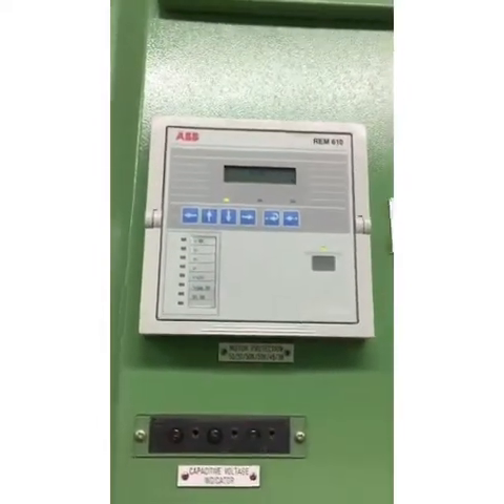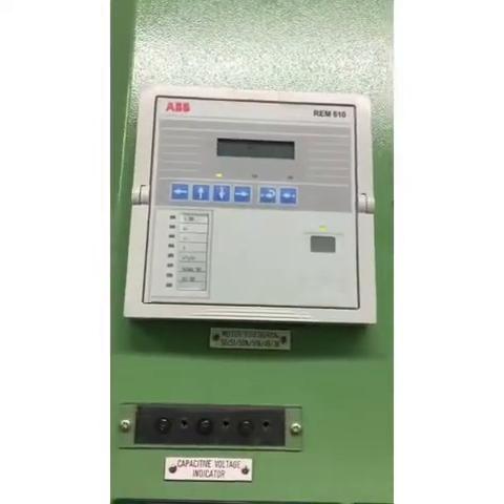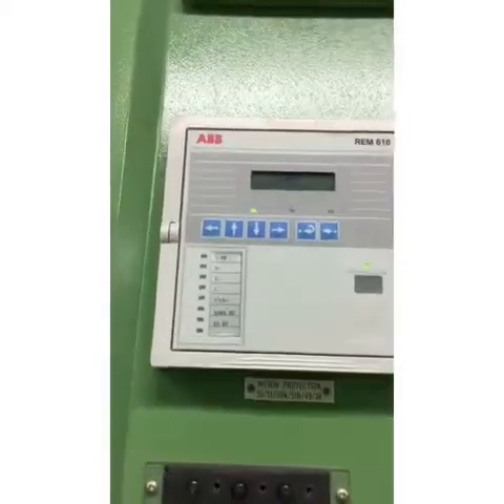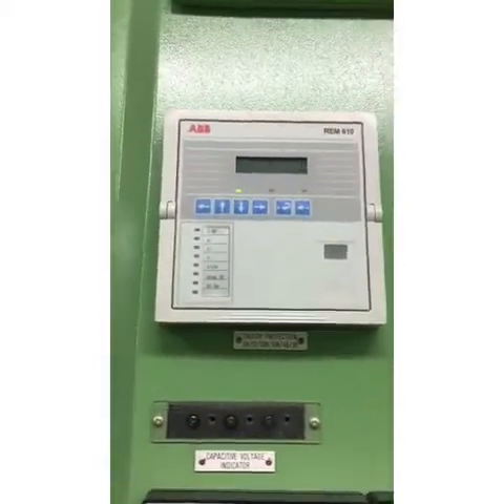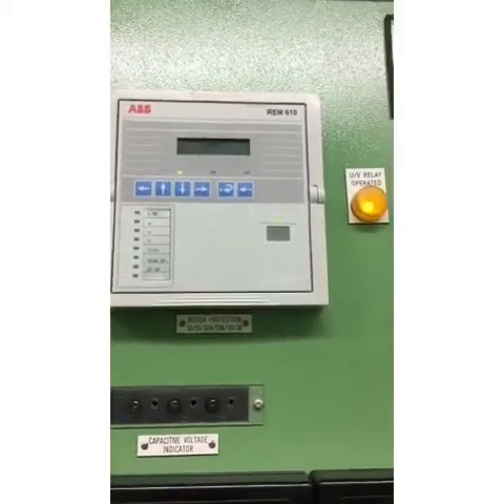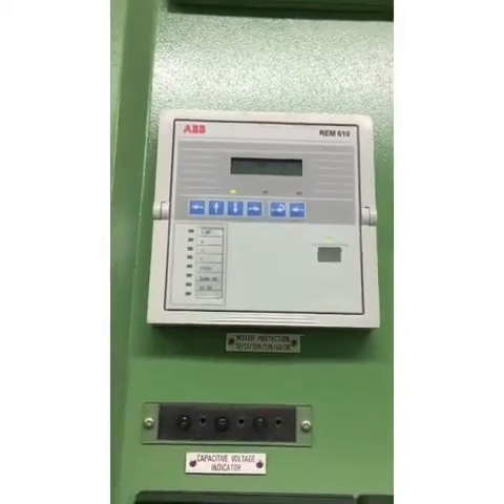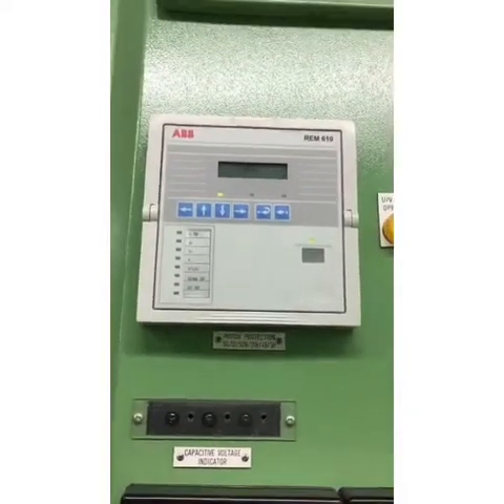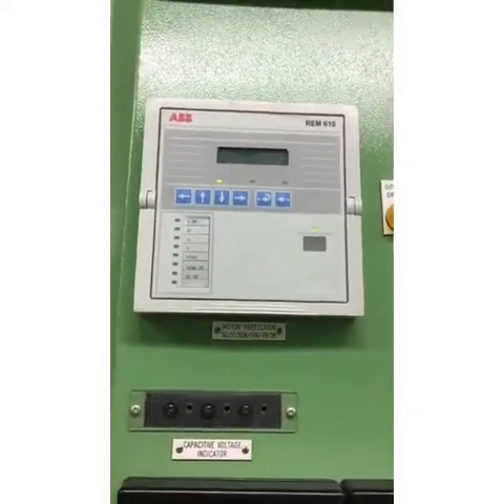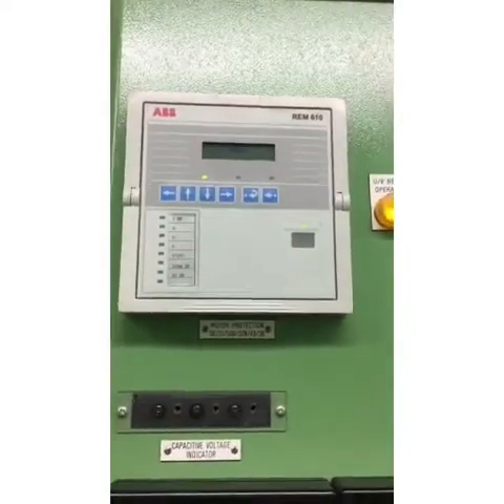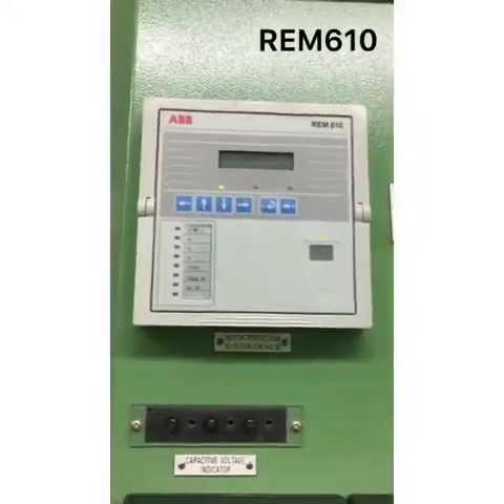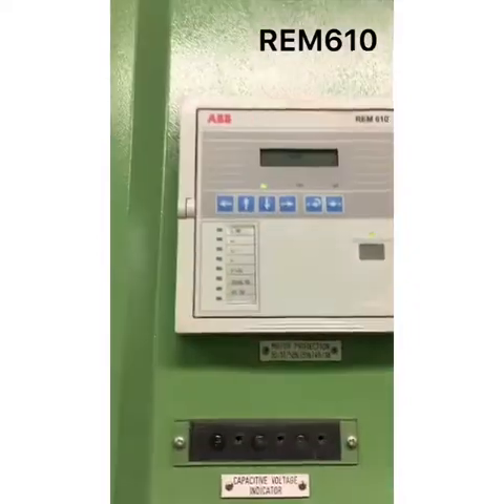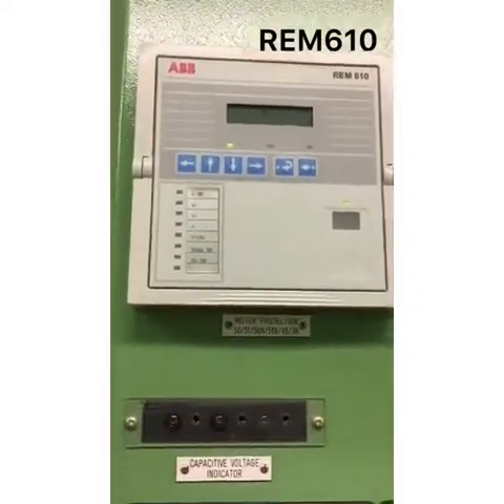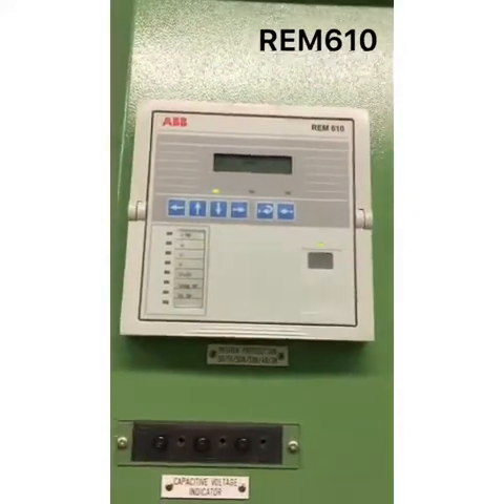In stage 3, we usually have 3 types of relay. We know the load in medium voltage: we have either motors like fans and pumps, or we have transformers, the BFDs. For motors, we have 2 types of relays. We have this one, REM610, for less than, I think, 2 megawatt motors, and we have REM543.